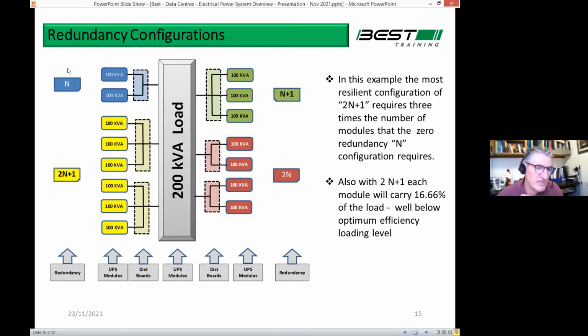With an N system, you just put in the bare 2 modules, okay? So you have 2 modules. If one of those fails, you've lost the load. So for most data center solutions, the minimum level of resilience is N+1. So they meet the need, they put in 1 spare module. So in this case, you need 3 100s, 2 of them meet the need, and then you have 1 spare one. That's what the +1 means.